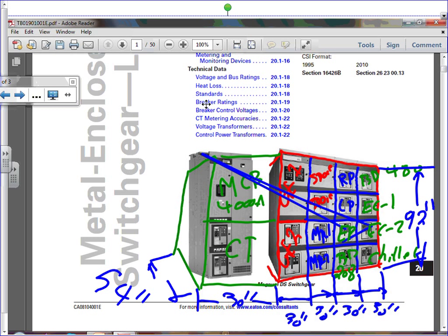And you're looking at it right here. What's the advantage of this, guys? The advantage is, if one of these circuit breakers malfunctions, and each one of them could be $10,000, you can draw out that circuit breaker, put it in a cart, and wheel it all the way to the manufacturer or to your technicians to fix it, and you will have a spare one. They always have a spare one. They plug the spare in, adjust the settings on it, and you're up and running within seconds.